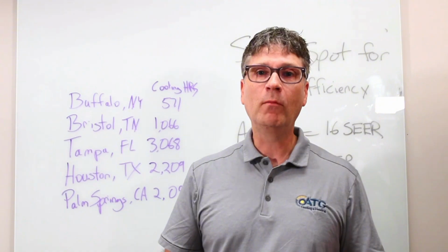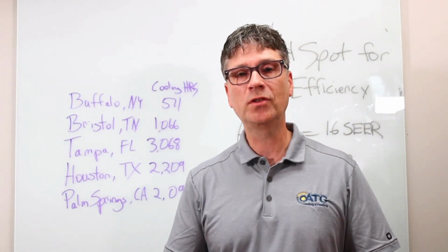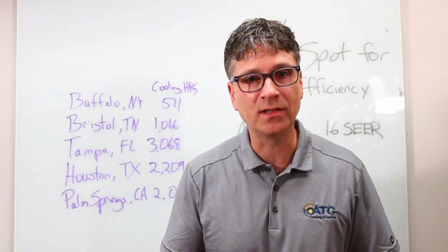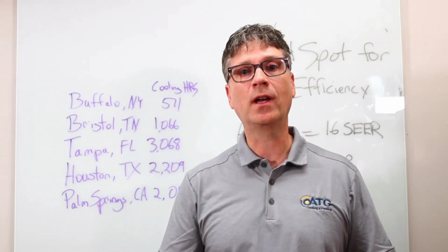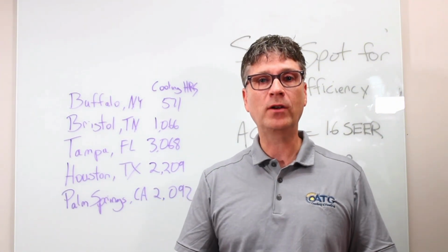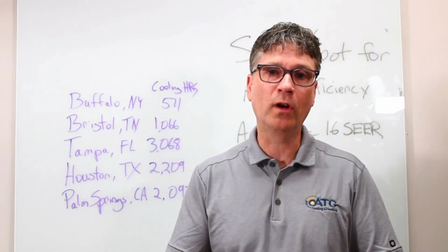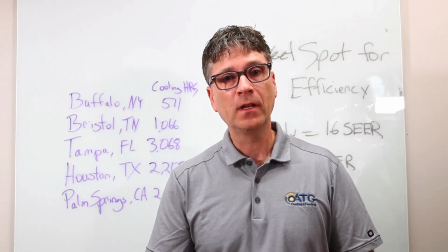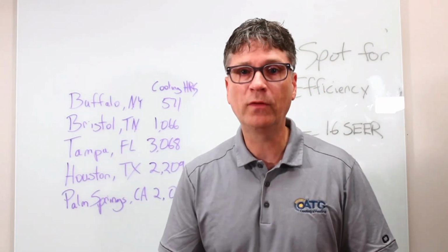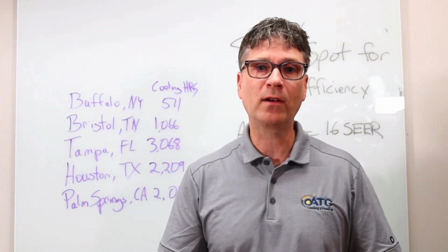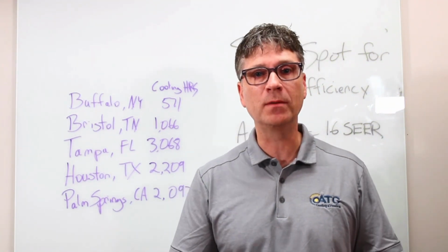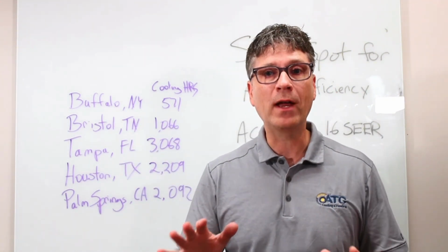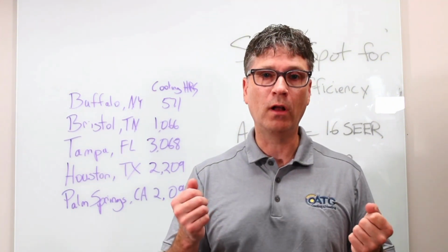It should be said that there are more reasons to choose higher efficiency than just the absolute cost to operate the AC. For example, at about 16 SEER for most manufacturers, you start to encounter two-stage units. These models do a better job removing humidity and will often run at just the first, lower stage, resulting in quieter operation. At 17 SEER and above, you will find variable output units. These models have many stages and can vary their output to match the conditions of your house and the temperatures outside. They do an even better job removing humidity and are overall very quiet.